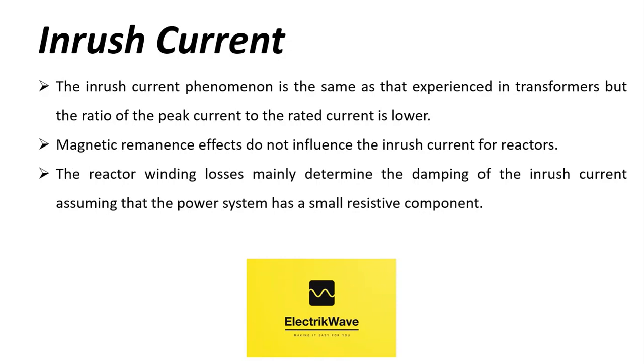The inrush current phenomenon is the same as that experienced in transformers, but the ratio of the peak current to the rated current is lower. Magnetic remanence effects do not influence the inrush current for reactors. The reactor winding losses mainly determine the damping of the inrush current, assuming that the power system has a small resistive component.